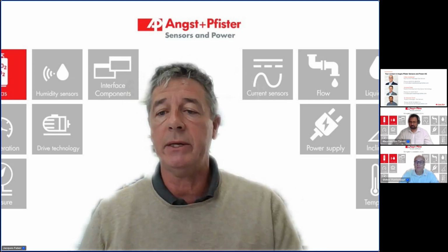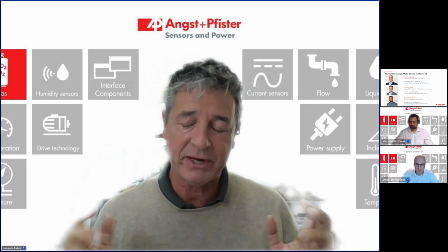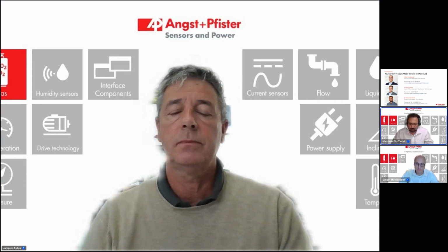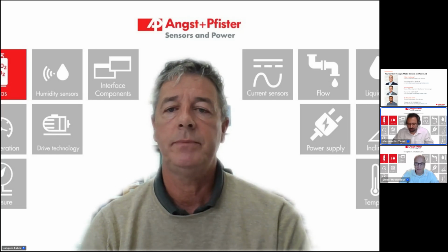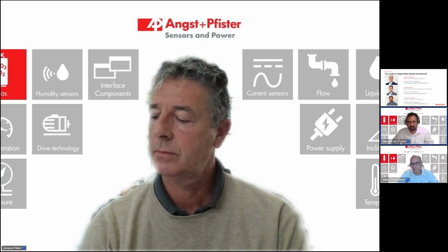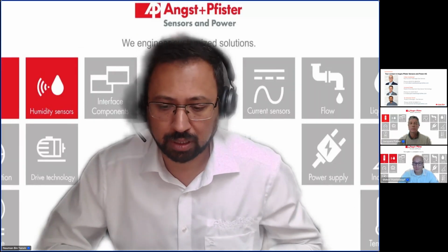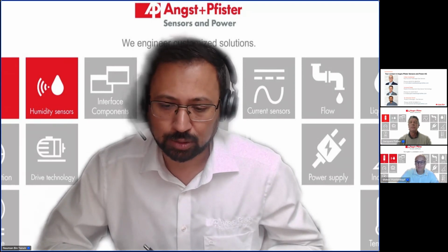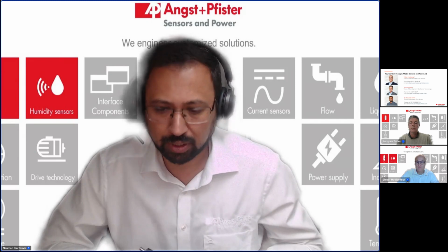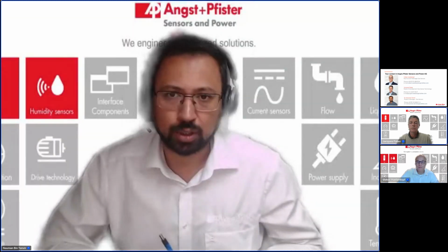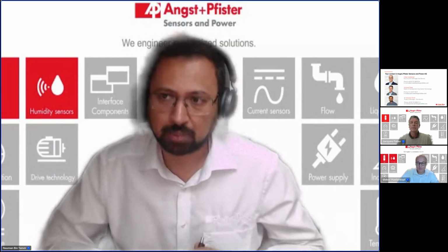But others are quite low, and if you know that you have the clearly defined gas, you can calculate so as to eliminate this effect in a calculatory way. Maybe I can add something here. We have a lot of other technologies in our portfolio, and what Jacques is referring to as very low is extremely low in comparison to other technologies that we have available for oxygen sensing. So there are some gases which have an influence, but in comparison to other technologies, the influence is extremely low. So we can clearly say in this case that paramagnetic oxygen sensing is very selective to oxygen.